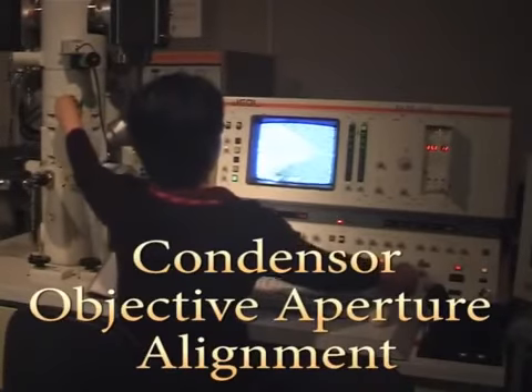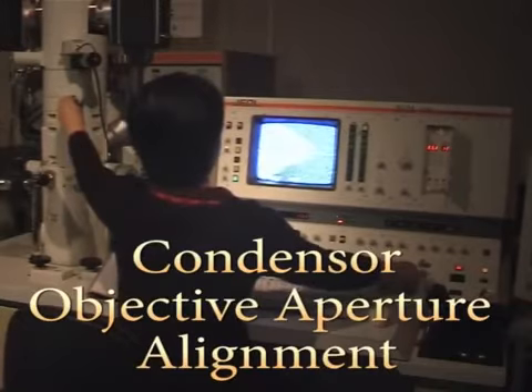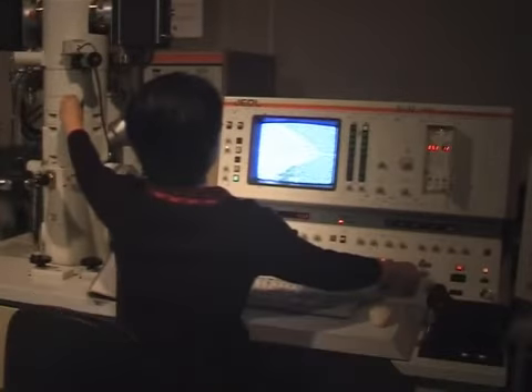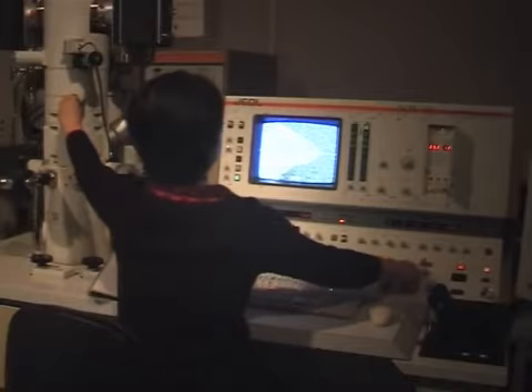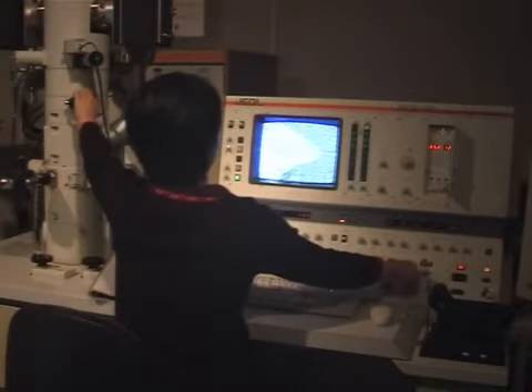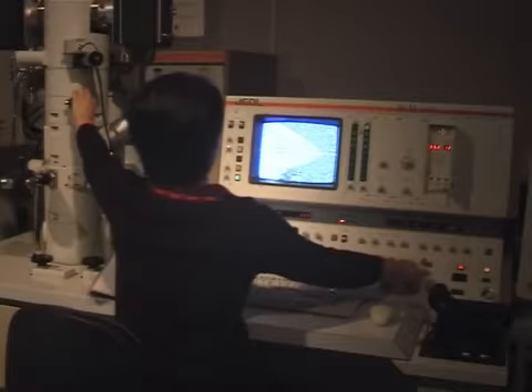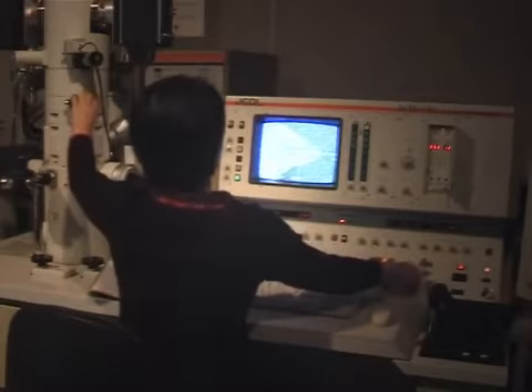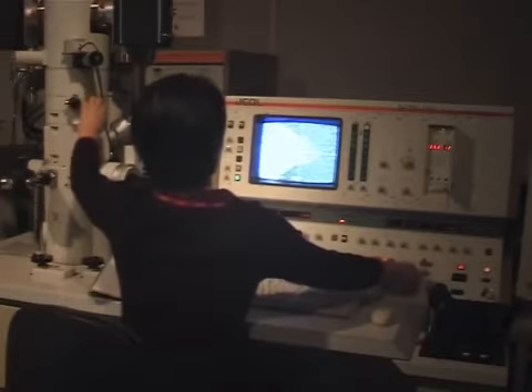Select ECP from the EOS mode area. Rack the ECP focus back and forth using fast movements, while adjusting the objective aperture alignment knobs on the column until image movement is reduced to a minimum. Only small adjustments of the knobs are required. Do not turn or adjust the small handle below the aperture knobs.